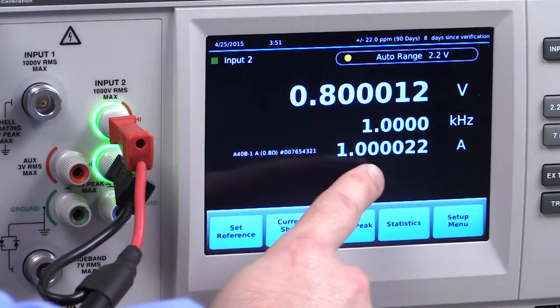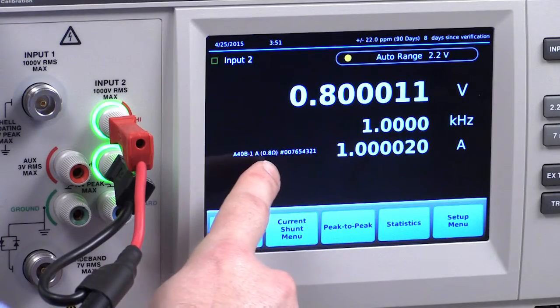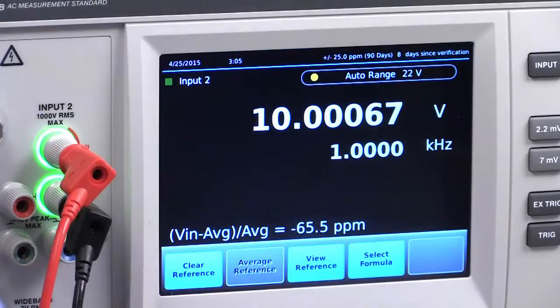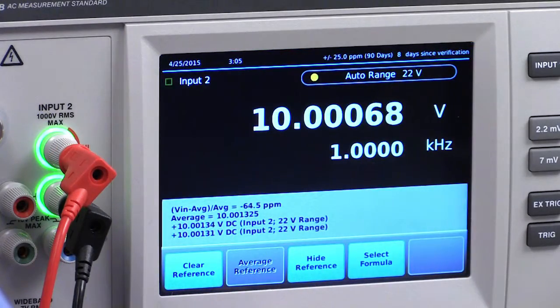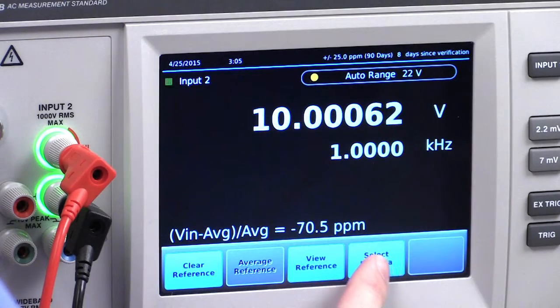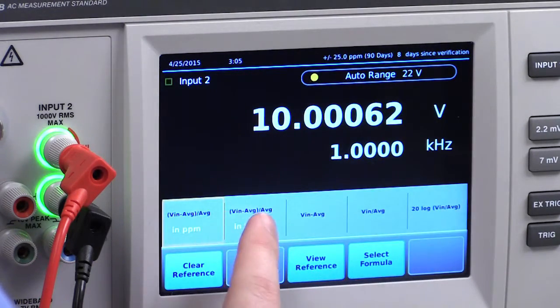When using a current shunt, the 5790B displays both the voltage and current measurements along with the shunt information. For transfer measurements using a DC transfer, the measurement can be viewed on the screen in many formats.